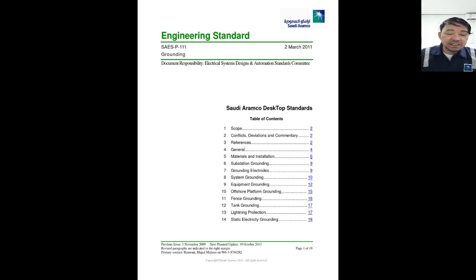For the impedance grounded system above 1 kV, this is the requirement as per SAES-P-111 8.3.1. The ground resistance of made electrodes, ground rods, and or grounding grid used for system grounding shall not exceed 5 ohms. Under a solidly grounded system above 1 kV, as per SAES-P-111, paragraph 8.4.1, the ground resistance of made electrodes, ground rods, or grounding grid used for system grounding shall not exceed 1 ohm.